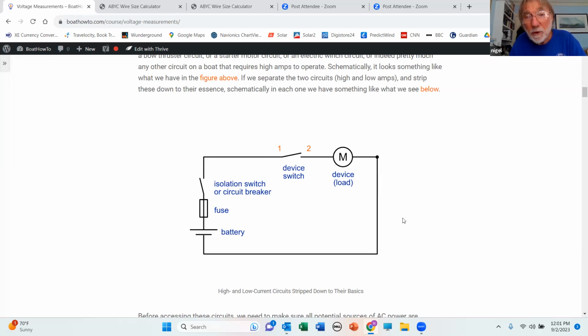We're on battery negative, so negative goes all the way here, and then we get our meter lead attached to the other end of this long meter lead, and we go here. We should read battery voltage because we've got positive to here, and we've got negative to here. And we've taken our long meter lead from negative to positive. We should read battery voltage. Let's say we don't. So we go back, we find a connection in the circuit somewhere back here. We touch that, we're still not getting battery voltage. We come back, we're still not getting battery voltage. We come back, all of a sudden we're getting battery voltage. Between the last place we took a reading and this place, we know there's a break in the circuit.